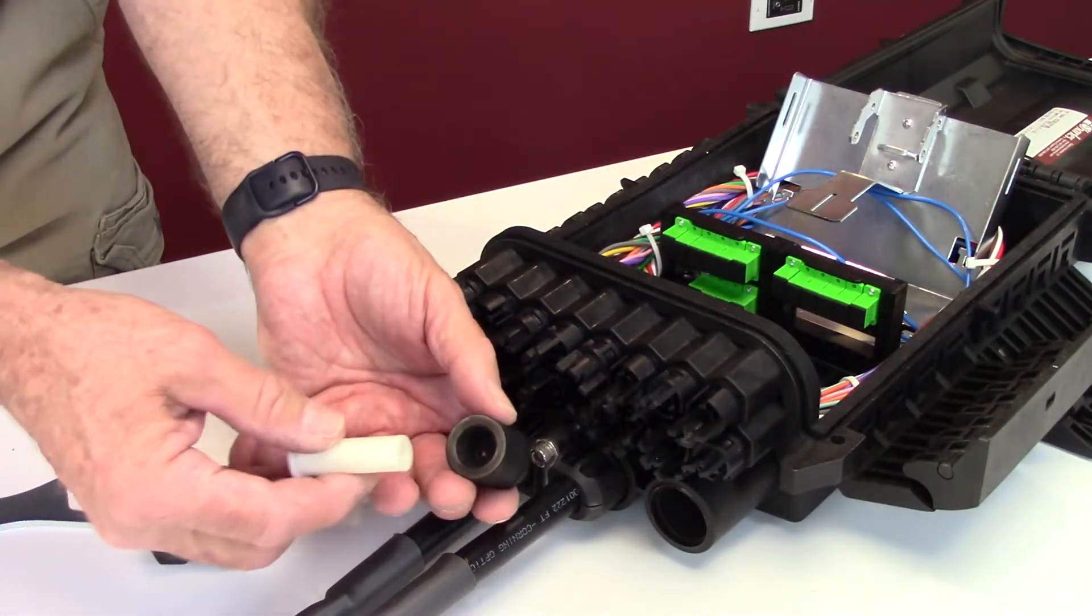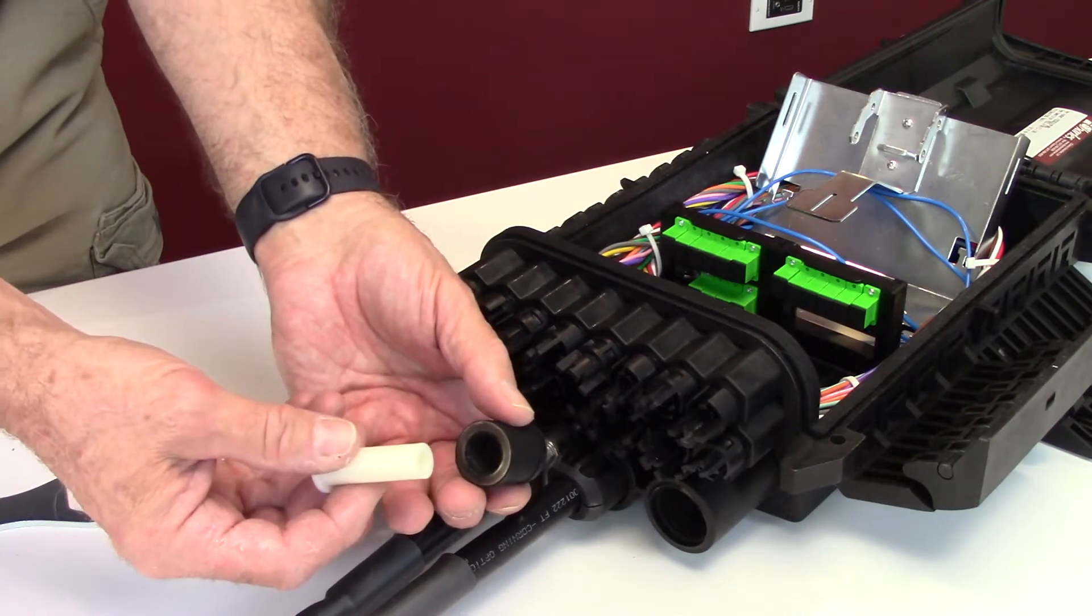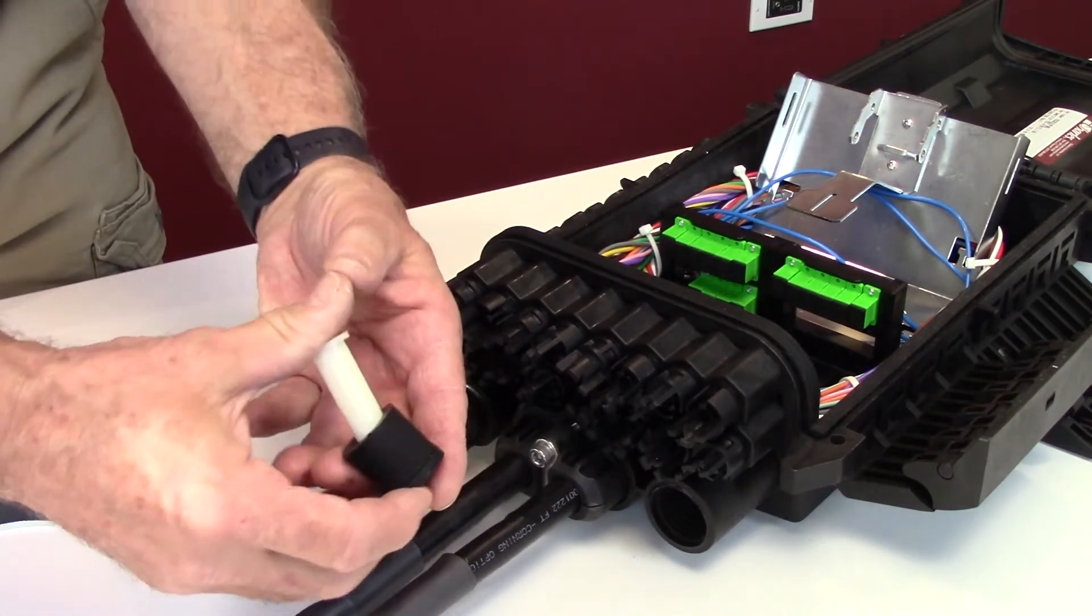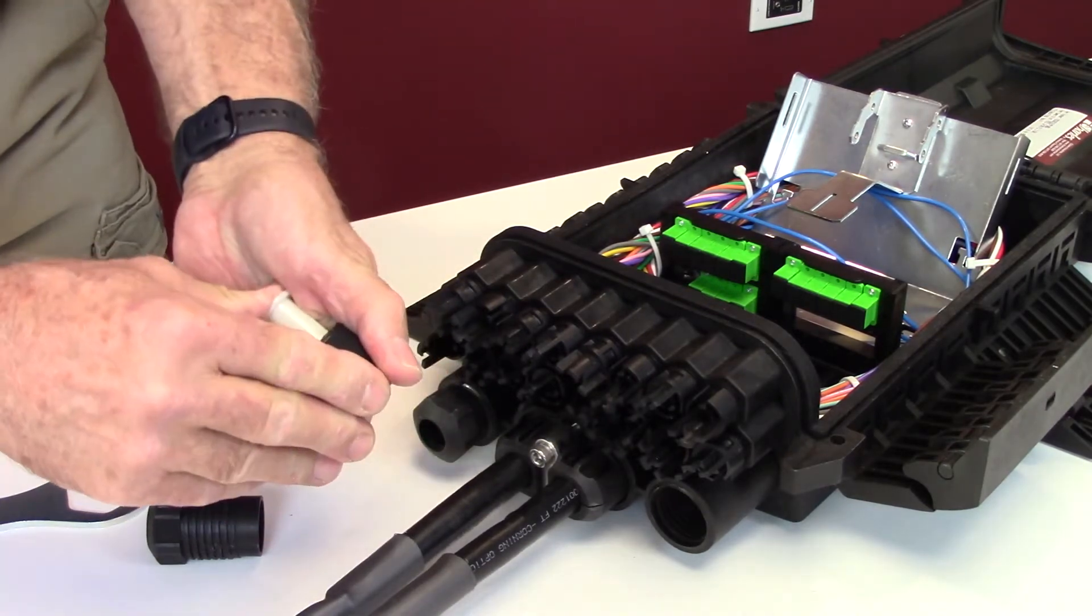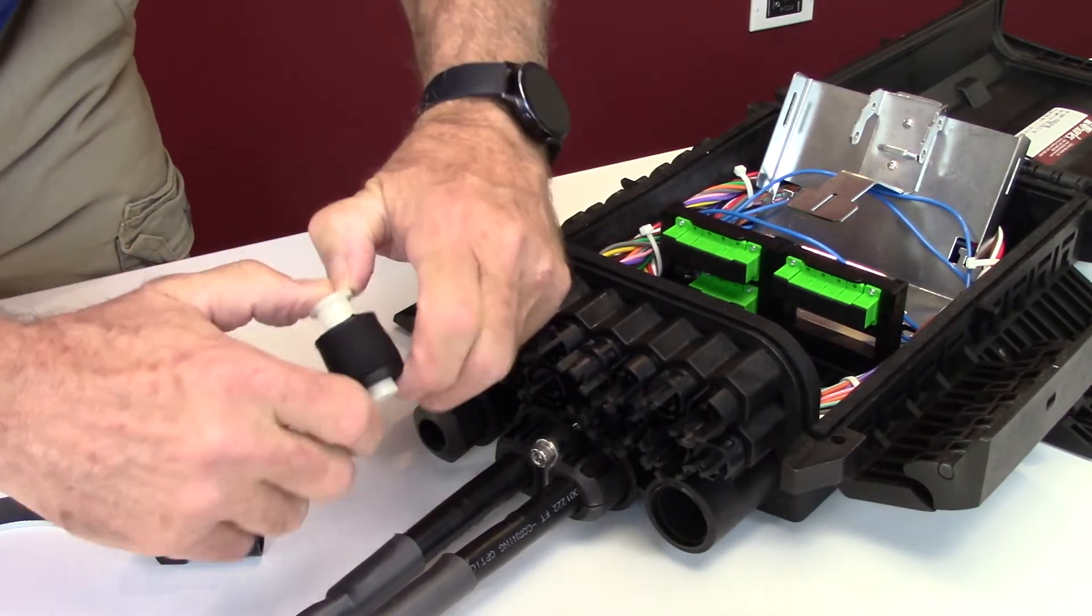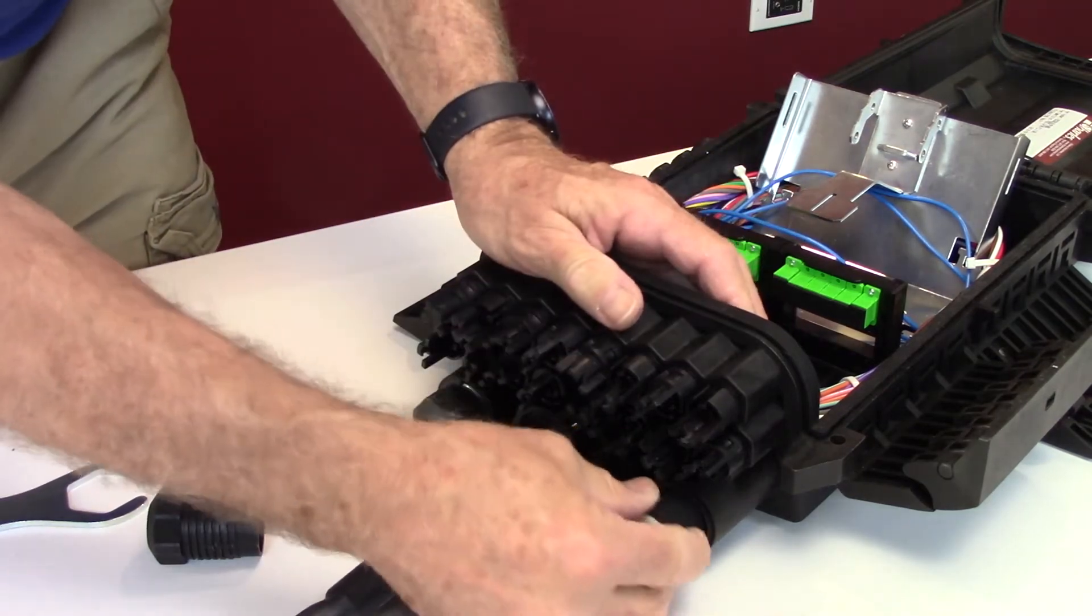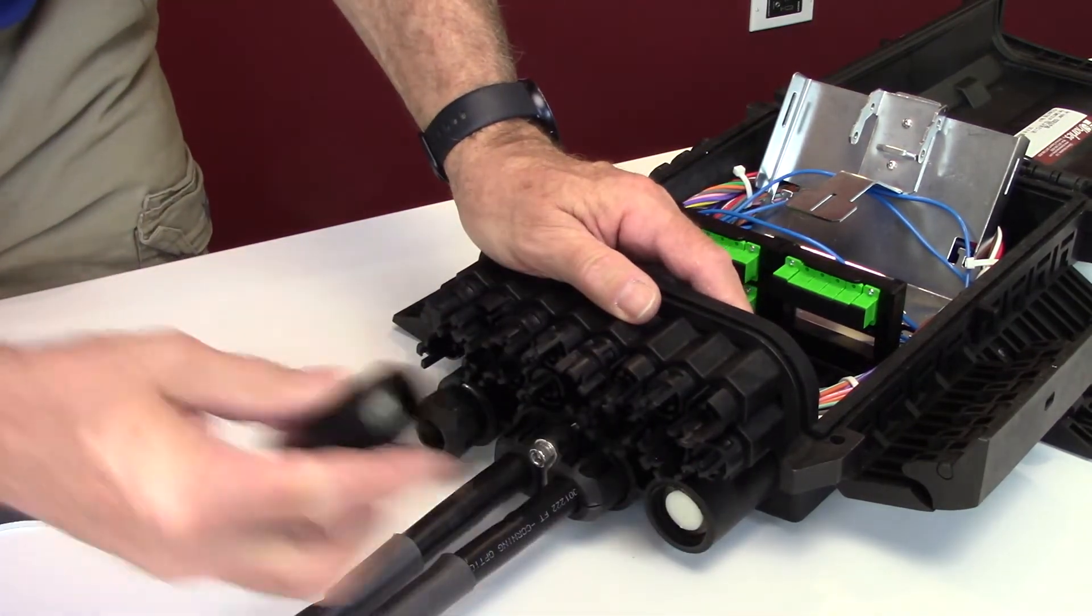All unused branch cable ports must be sealed with a plug and grommet. To seal the cable port, push the white plug through the grommet and then install the assembly into the port. Tighten the branch port plug with the supplied wrench.